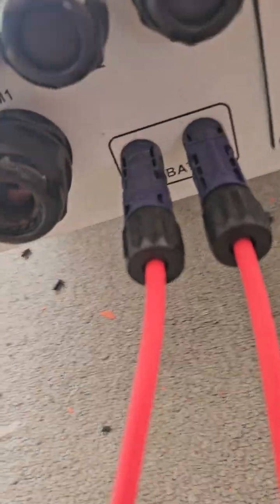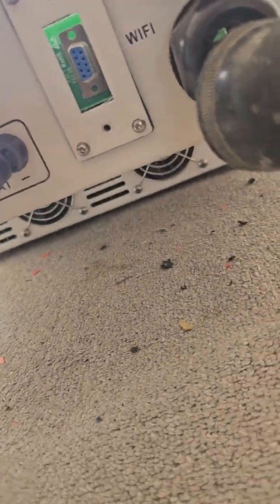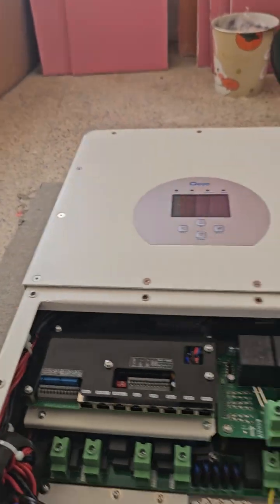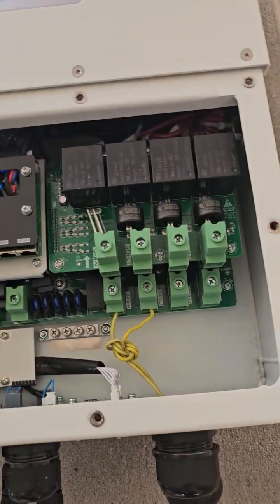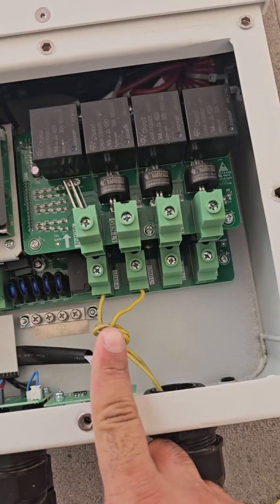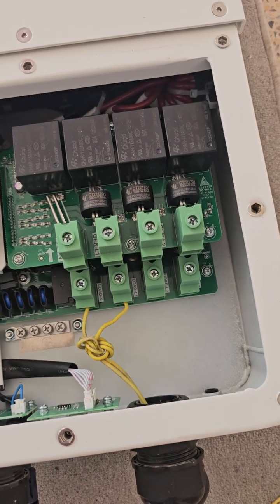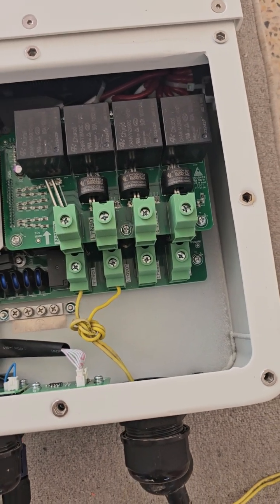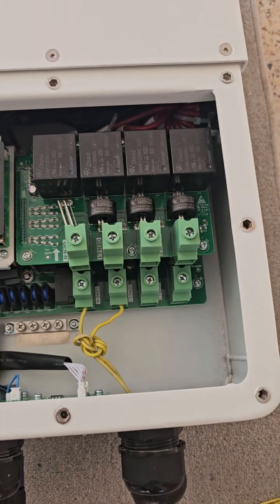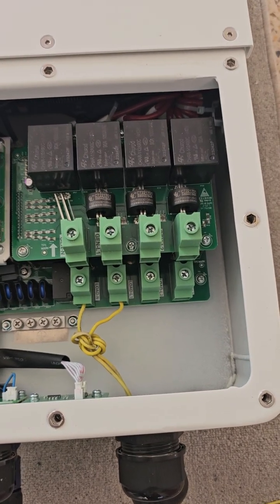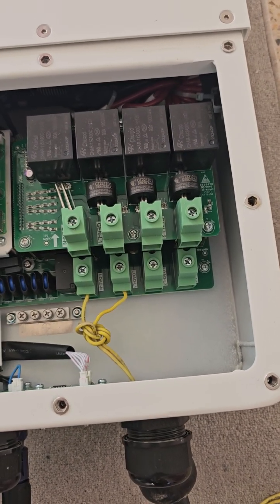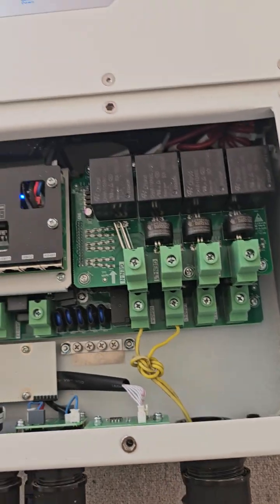And when you do that without any communication, as you can see, all the batteries are connected in series, and I have positive and negative connected via MC4 connectors to the battery positive and negative terminals of the inverter. It's a 3-phase inverter, so I have an N and 3 L's: L1, L2, L3. I believe it's also available in split phase, and for the US market I don't think it's available in single phase.